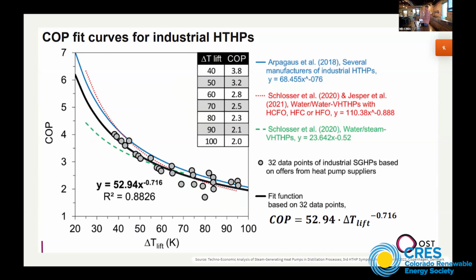If you're doing an air source heat pump, you can be down to -10 degrees Fahrenheit, and you're trying to raise it all the way up to 212, 250 degrees Fahrenheit. That's a huge lift, a huge amount of energy you need to put in to get up to steam temperatures. Conversely, if you're trying to take a 200 degree waste heat stream to 250, that's a much smaller delta, much smaller lift, and you can do that with much higher efficiency. That's frankly why a lot of these initial attempts and initial focuses were on using waste heat streams as the source for that heat.